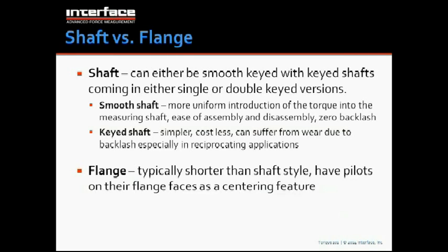If you have, say, a motor and a gearbox and they both have shafts, then a shaft style sensor may be the best choice. Keyed versus smooth shafts. A smooth shaft works quite well with the appropriate kind of coupling. The benefit of a smooth shaft is it applies the torque to the shaft in a uniform manner about the entire perimeter of the shaft. Or with a keyed shaft, you're actually applying a force at the keyway, and that translates into a torque, but that isn't necessarily a true torque.